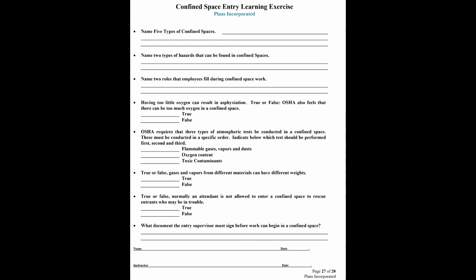Number 5, OSHA requires that 3 types of atmospheric tests be conducted in a confined space. These must be conducted in a specific order. Indicate below which tests should be performed first, second, and third. Flammable gases, vapors, and dust, oxygen content, toxic contaminants. Number 1, oxygen content. Number 2, flammable gases, vapors, and dust. And number 3, toxic contaminants.